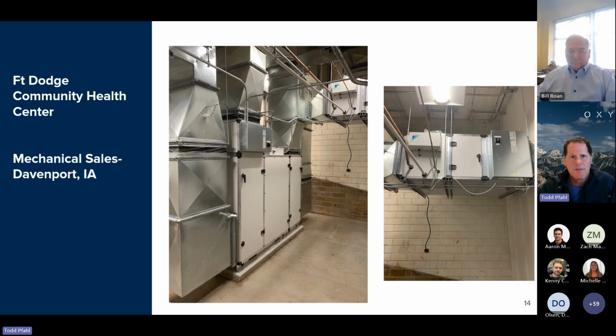This is an example of some flexible duct connections that we can do. So we can optimize ductwork, fit these units through small hallways, down stairways, through doors, through elevators. Again, it gives you a lot of flexibility of where you place your ventilation solution in buildings. And it's an example of a coil module that's up and out of the space.